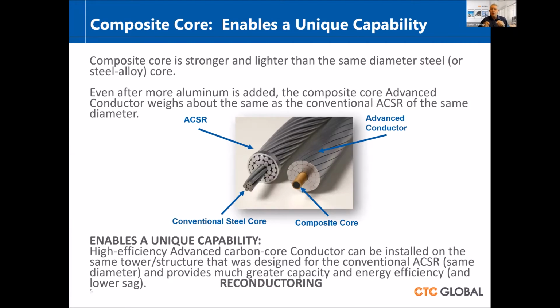This composite core actually enables a very unique capability. That's why it's special. The composite core you see in the picture there replaces the conventional steel core in the traditional ACSR or other conventional type conductors. That composite core is much lighter, much stronger, much lower sag. The thermal expansion is so much lower than the steel.